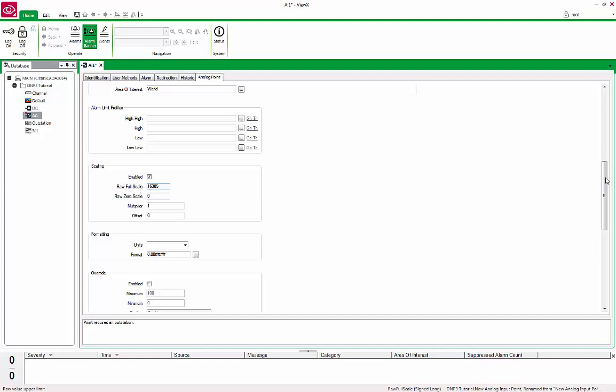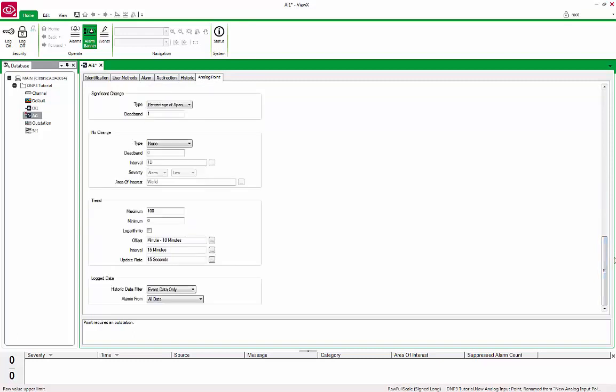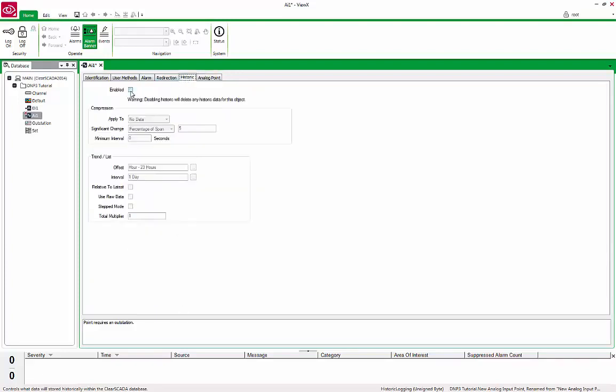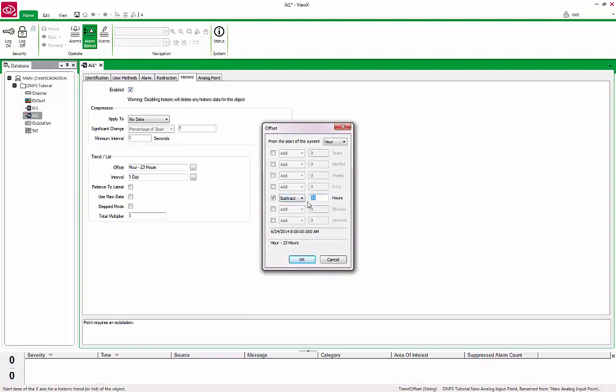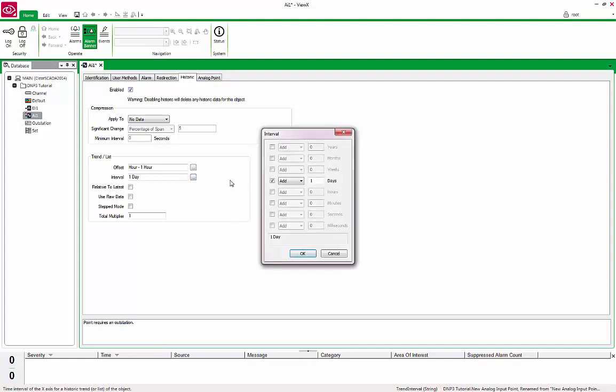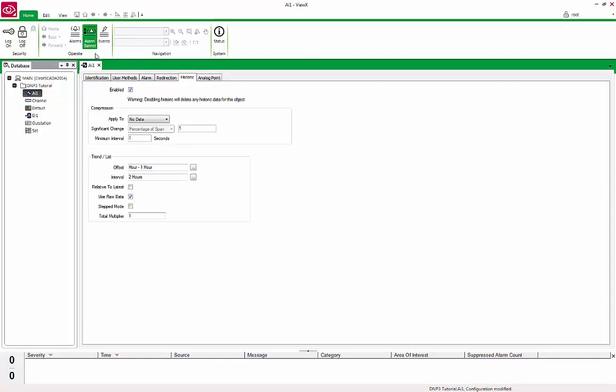Next, scroll down further to the Log Data section, and under the Historic Data filter, select Static and Event Data from the drop-down list. This will allow all informational data to be stored in ClearSCADA as History. Lastly, click on the Historic tab and check the Enabled box. Under the Trend List section below, set the Offset to H-1H and the Interval to 2H. This will default the Trend Time Span to start from the beginning of the last hour with a span of 2 hours. Finally, check the Use Raw Data box at the bottom. This tells ClearSCADA to display trends using the raw samples rather than processing the data prior to sending it to the client. Save and close the form.